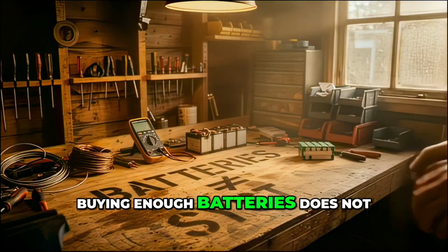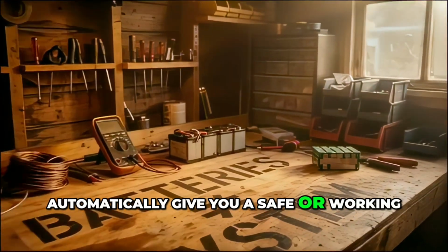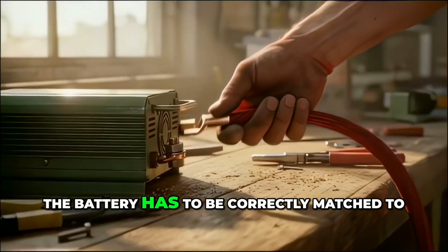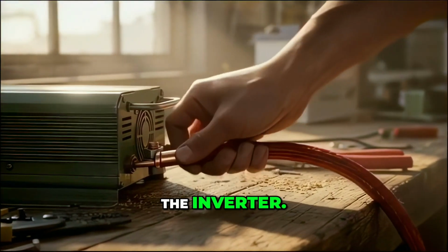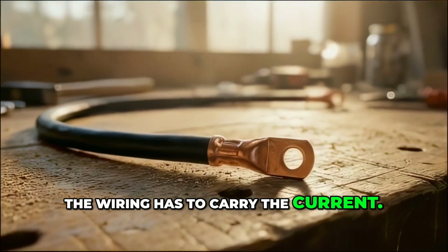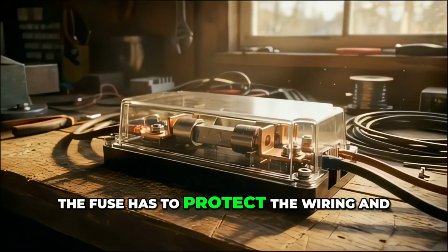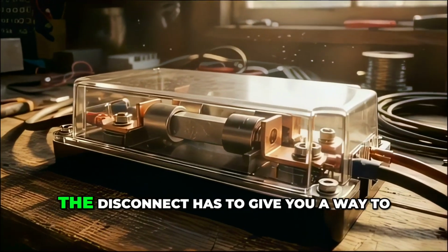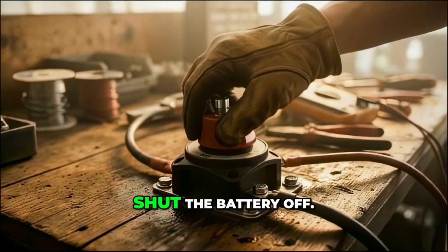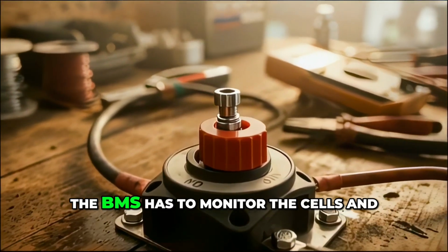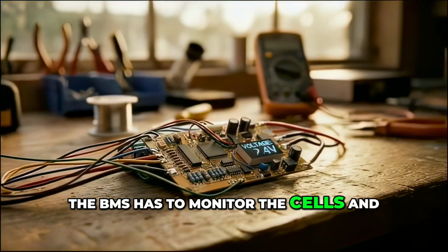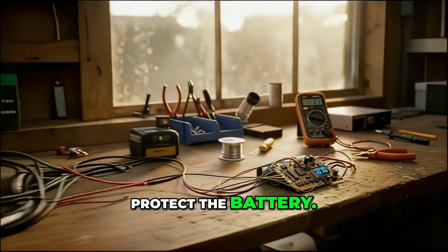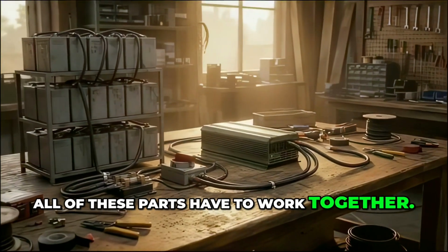This is an important point for new DIY builders. Buying enough batteries does not automatically give you a safe or working system. The battery has to be correctly matched to the inverter. The wiring has to carry the current. The fuse has to protect the wiring and equipment. The disconnect has to give you a way to shut the battery off. The BMS has to monitor the cells and protect the battery. All of these parts have to work together.